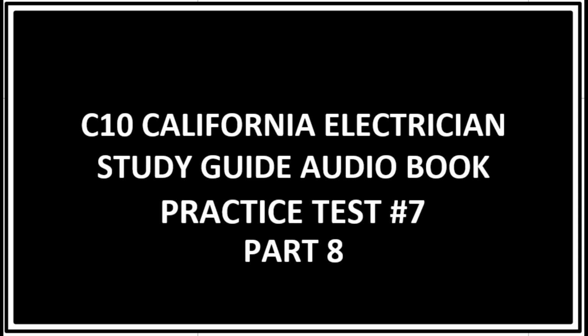Question 91. The ampacity requirements for a disconnecting means of X-ray equipment, if greater than the long time rating, shall be based on 50% of the input needed for the momentary rating of the equipment.